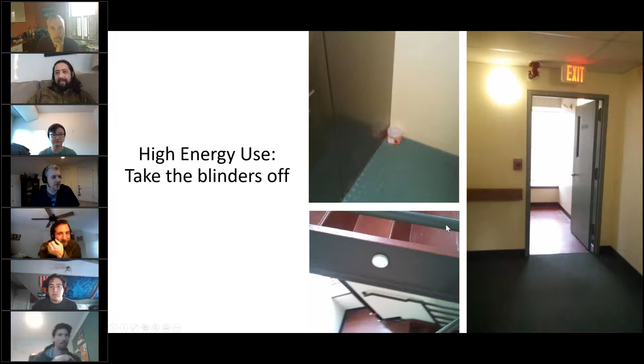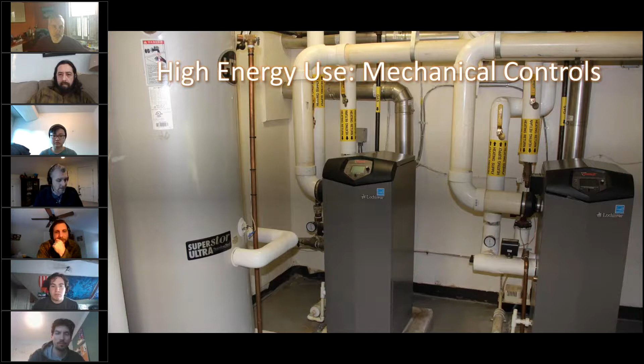Okay, so I start walking towards the boiler room, which is on the lower level. And I get down there and I realize that for any of the boilers in this facility, this building, the other building, warm weather shutdowns are not really implemented. The outdoor air temperature resets are not implemented. Pumps aren't controlled. They're just on at full speed, even though they're variable speed. So it's kind of like, well, these things are able to produce 180-degree water when it's 75 to 80 degrees outside. Well, not right now, but like in the summertime. Oh, there's a big problem. Okay, we can fix that. And the maintenance guy says, okay, I'm going to leave you alone now inside here. And he had to go fix something else. But before he left, I said, well, what's this hatch in the floor?